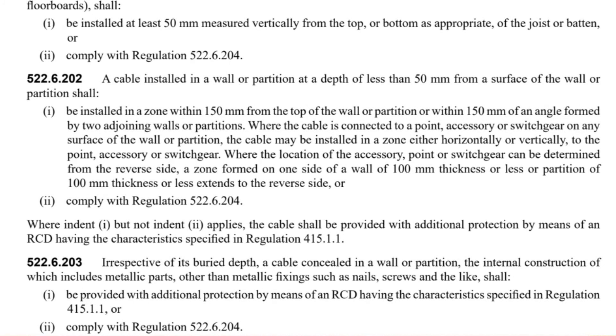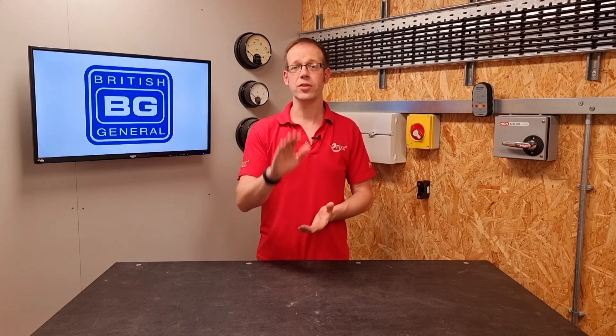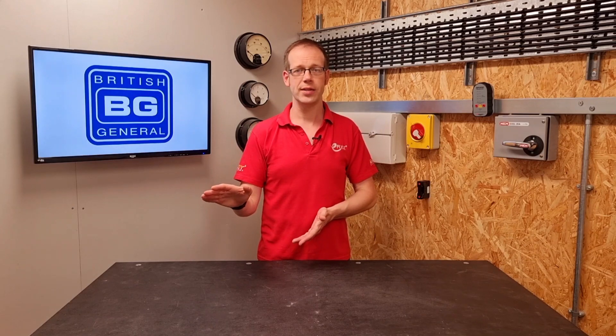That's why there's another layer of protection required at the bottom of 522.6.202. Where indent 1 but not indent 2 applies, the cable shall be provided with additional protection by means of an RCD having the characteristics specified in regulation 415.1.1, which basically means a 30mA device. So if you're installing twin and CPC into an installation less than 50mm deep and it's in the prescribed zones, you have to use RCD protection. It's really important to note that prescribed zones and RCD protection must be used together to comply. You can't miss out RCD protection because the cables are in the zones, and you can't install cables buried just anywhere and rely on RCD protection to comply. Both must be used in conjunction with each other.